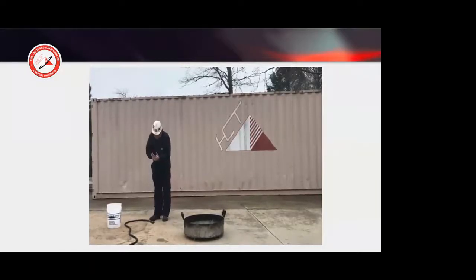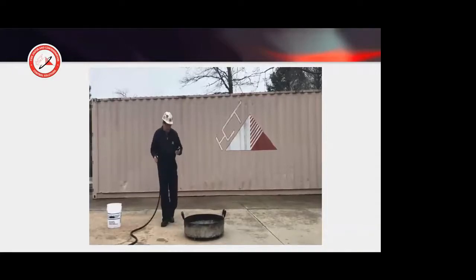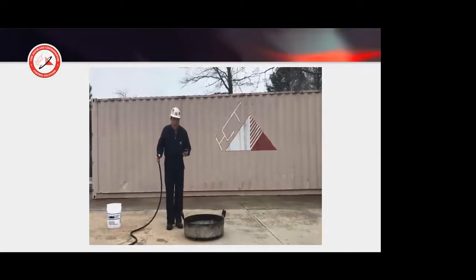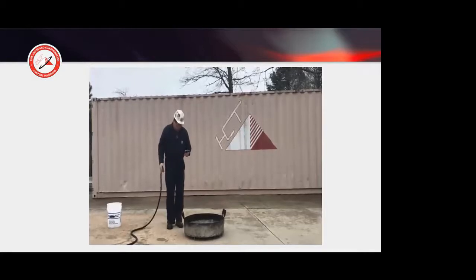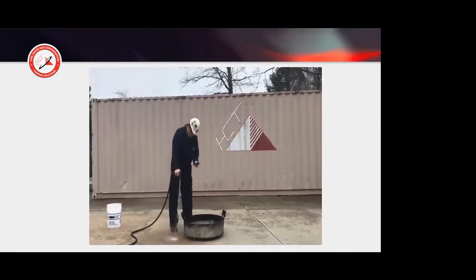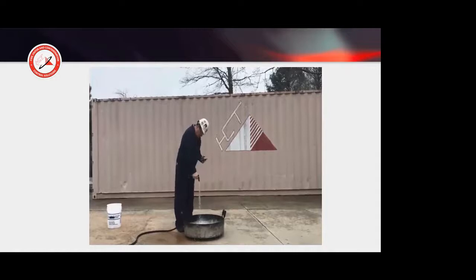So we've put in this case a gallon of gas. We have now mixed in 1 pint of the agent. And now I have a 5 GPM nozzle. So we're going to apply water in here for 1 minute. And that gives us that 1:8:40 ratio.